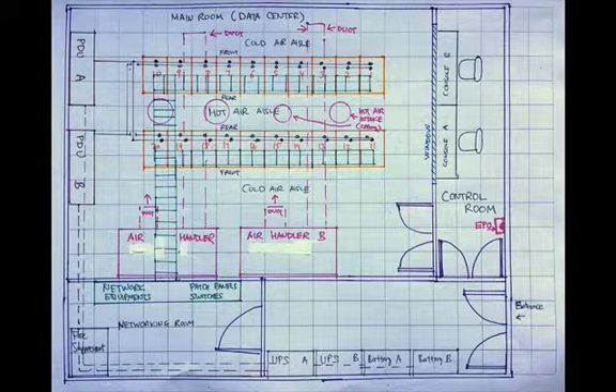The overhead installation was chosen over the raised floor installation because it was a better fit for the small data center and had the benefit of lower installation costs and less complexity. As a result, structured cabling is installed above, supported and routed by ladder racks. Power receptacles are housed in metal raceway and secured from the ceiling and suspended from above. Also, there are overhead ducts on the ceiling to draw the hot air from the hot aisle. Even though the racks are not fully populated, all cables are pre-wired for future installation.